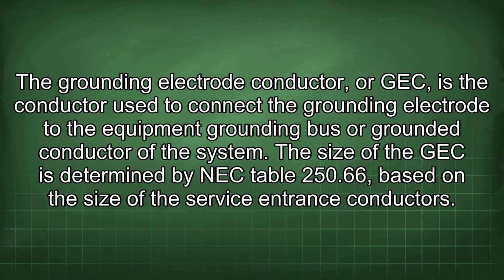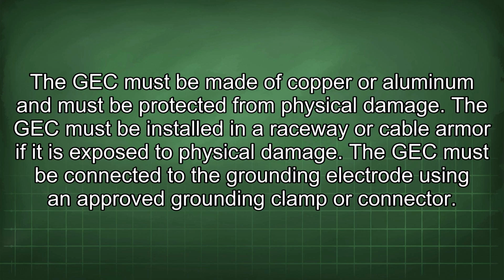The grounding electrode conductor, or GEC, is the conductor used to connect the grounding electrode to the equipment grounding bus or grounded conductor of the system. The size of the GEC is determined by NEC Table 250.66 based on the size of the service entrance conductors. The GEC must be made of copper or aluminum and must be protected from physical damage.